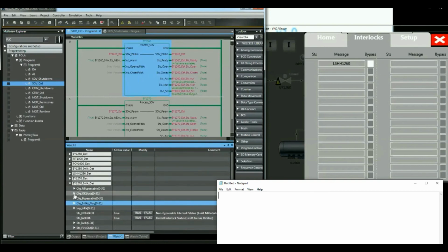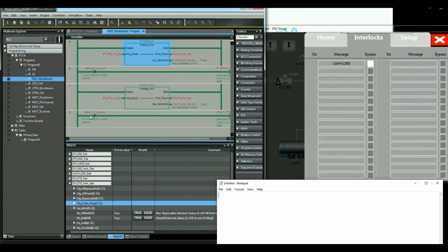And we picked the OK state to be 1 to make the system feel safe, rather than the OK state being 0, as you can see here. So right now we don't have any alarm, so that's good. That's 1. If we have an alarm, what we can do is this signal, which will make this off, which will shut down our valve. So this is a good approach. That's why if a fuse blows or some other things happen, you will know about it. Rather, if you go the other way around, like putting 0 as your OK state.